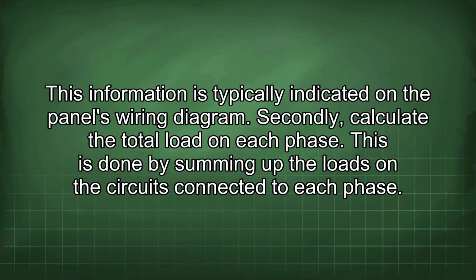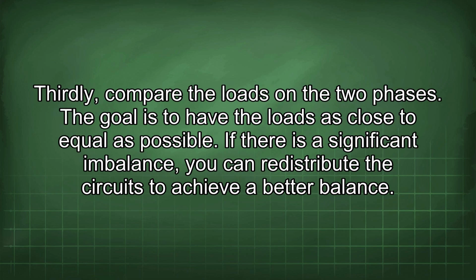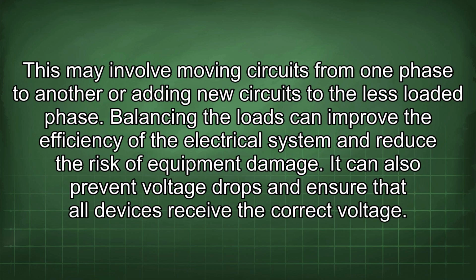Secondly, calculate the total load on each phase. This is done by summing up the loads on the circuits connected to each phase. Thirdly, compare the loads on the two phases. The goal is to have the loads as close to equal as possible. If there is a significant imbalance, you can redistribute the circuits to achieve a better balance. This may involve moving circuits from one phase to another or adding new circuits to the less loaded phase.